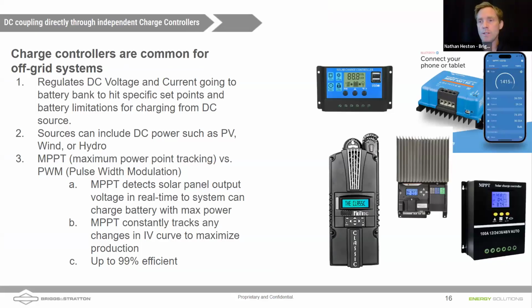PWM controllers. Now, in the top right of your screen, you're looking at a Victron unit. These are quite popular. In fact, I think the MPPT 150s from Victron are even more popular. But these devices allow communications as well. And so the MPPT is a more efficient way to get power out of your solar array. And what it does is it varies the amount of current it draws from a solar array. And that in turn, if you draw a little less current out of a solar array, it's going to increase the voltage output of the array.